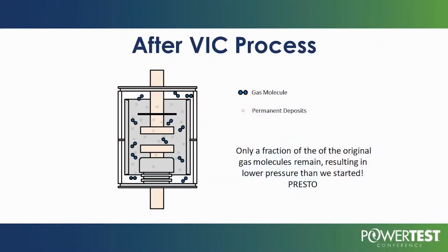Only a fraction of the original gas molecules will still be in the chamber after we've done this process. How many do we destroy? We don't know. The only thing we can see is ion current changing. Therefore, we know that the number of gas molecules inside have changed. And when we take the interrupters apart, we see the tarnished surfaces, we see a small brown residue, we see the things that have essentially happened inside by this process.